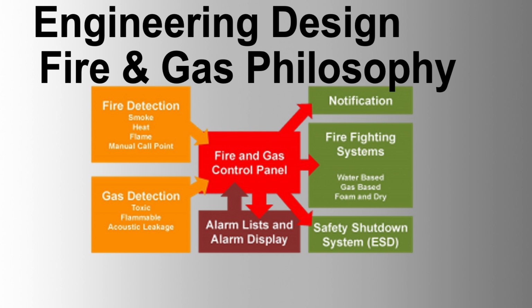Alarm lights, flashing beacons, and audible alarms should be provided in plant areas and buildings. The audible alarms should be routed through the PA system, with redundancy considered in the design. Automatic water spray systems should be activated by the fire and gas system, protecting identified equipment in plant and utility areas. Fire and gas detection and protection inside buildings. Each building and passive-cooled shelter should have a standalone addressable fire alarm control panel, FACP, that acquires local building detectors, beacons, and manual alarm call points.